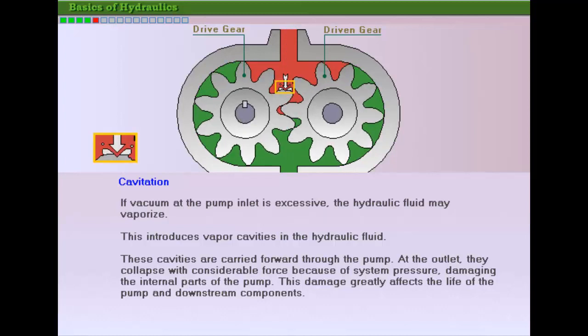This causes severe damage to the internal parts of the pump, and the resulting particles may cause damage to the pump and downstream components. Cavitation may be indicated by a noise in the pump.